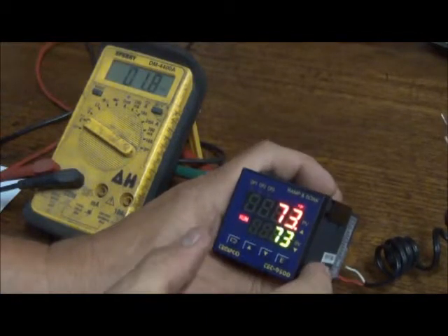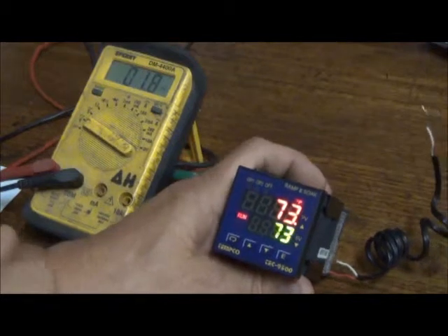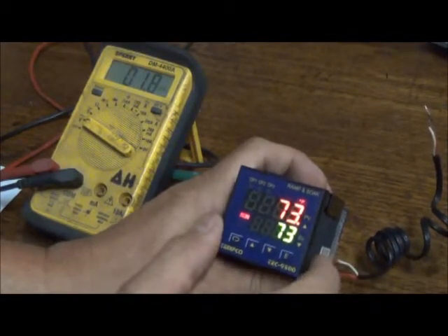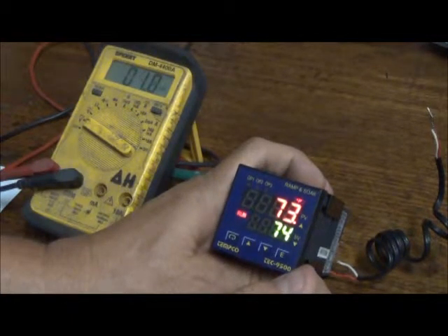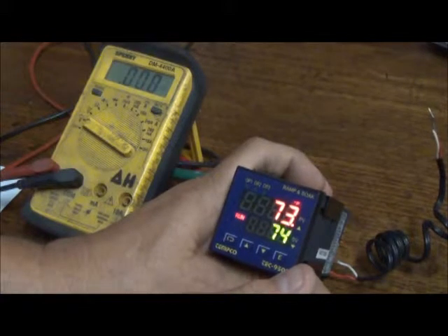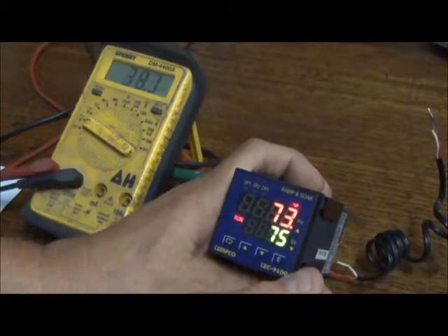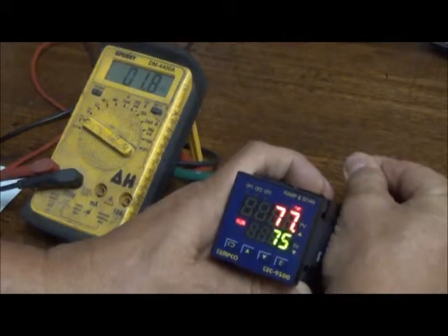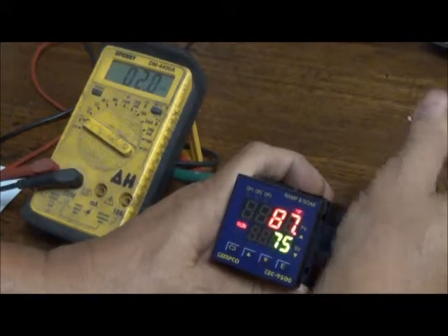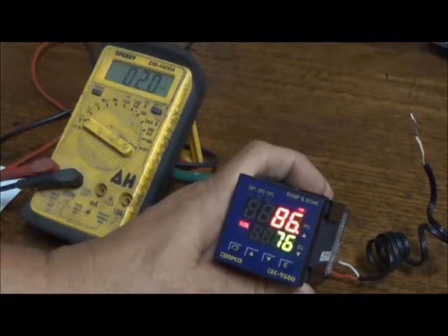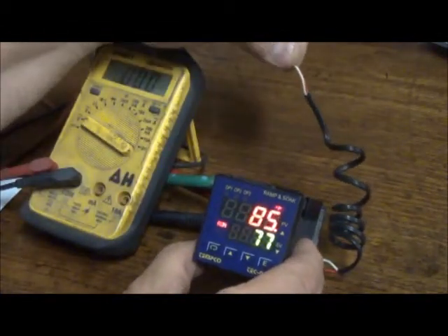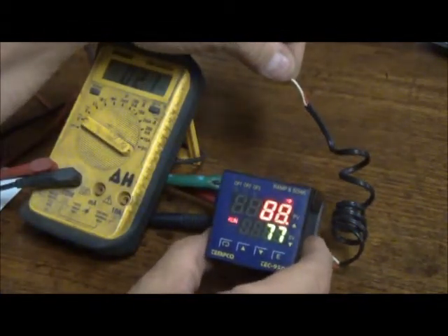Well, there you go. So it says run. All right, and the output's starting to flick on here because the temperature, see the set point going up. Okay. Hit 75 here pretty quick. So that's going up. And the output is beeping, but if I put a little heat on it, I can just grab it, and all of a sudden it says, hey, we're over set point. So shut her down. All right. So it's going up, I believe, at a set point at 80. Shut that guy up a little bit. That's how that works.